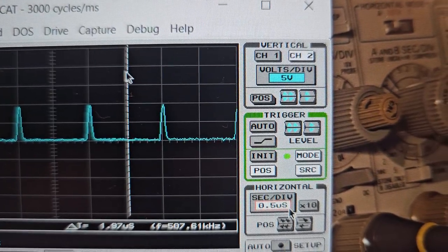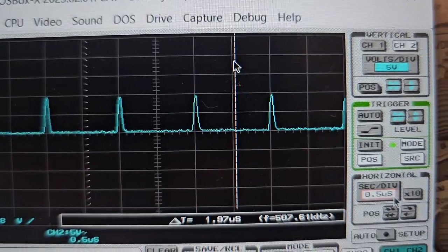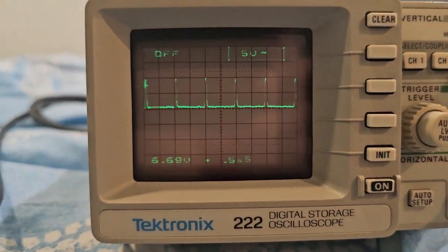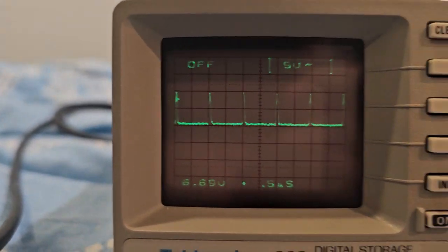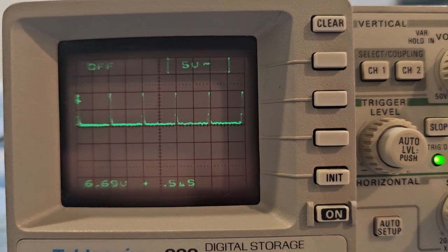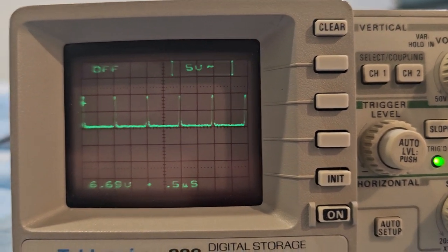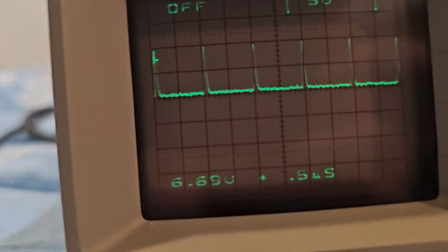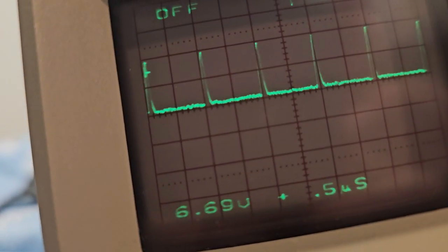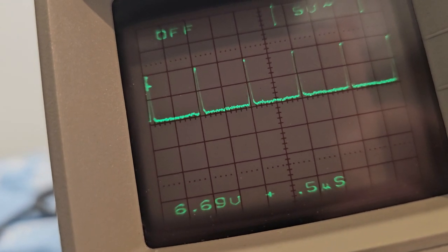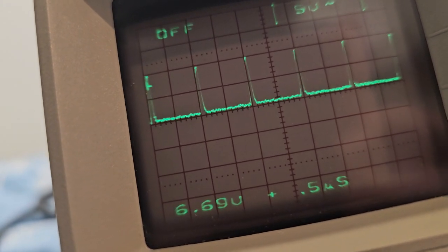They are very accurate. So the scope is indeed calibrated, not screen calibrated very well. As you can see, it's off on the graticules by just a little bit. It's still within spec, but just a little bit off. It has a really, really sharp trace, because it's a tiny CRT and Tektronix made excellent CRTs.